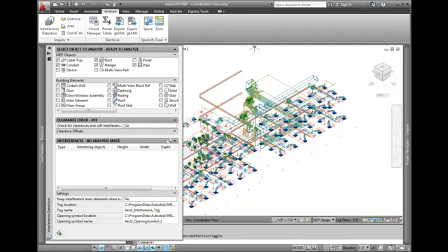If an interference is detected at a wall, you can tell the program to place an opening symbol. This lets the owner of the wall know that they need to add an opening to their elements to help with the clearance. I want to point out that the tool works with XREFs as well. All of these models are referenced in, so you can create a coordination drawing that contains all of the discipline constructs and check the entire project at once.